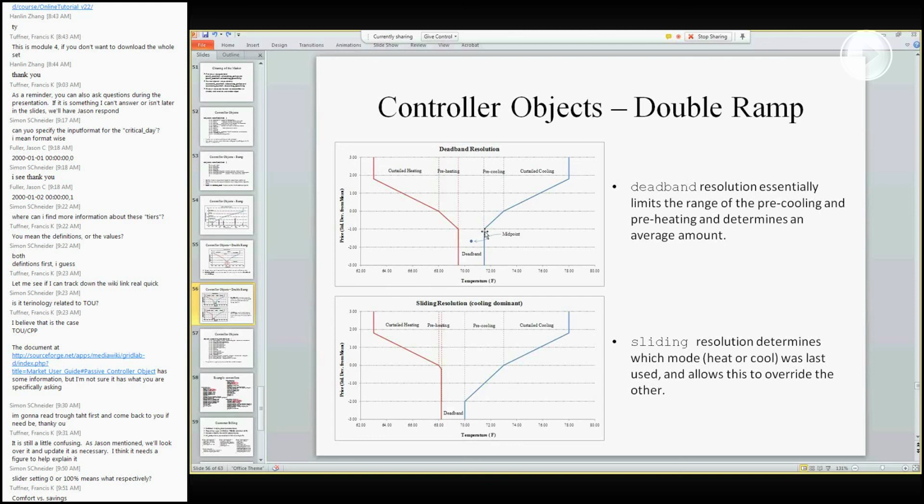This comes from our information from the Olympic Peninsula demonstration project, and it was kind of the most that we thought customers would actually respond, and that has a limit of Tmax of 5 degrees, Tmin of -3 degrees, with a certain slope setting that a lot of the maximum customers gravitated to in the original experiment. So it's our best guess at what that 100% might mean.